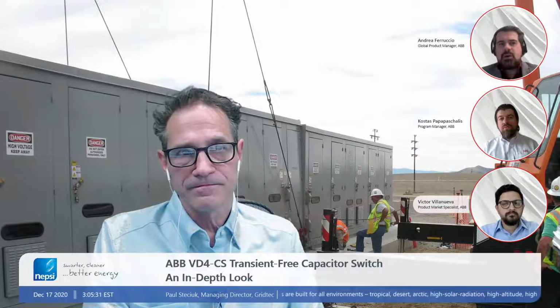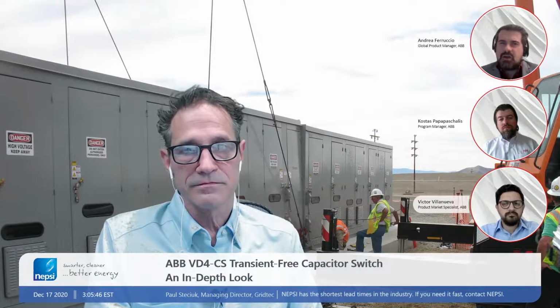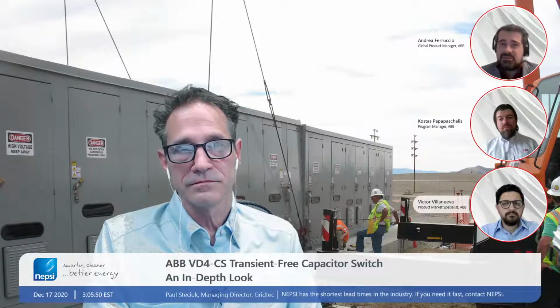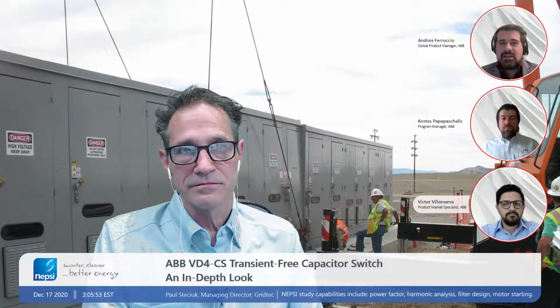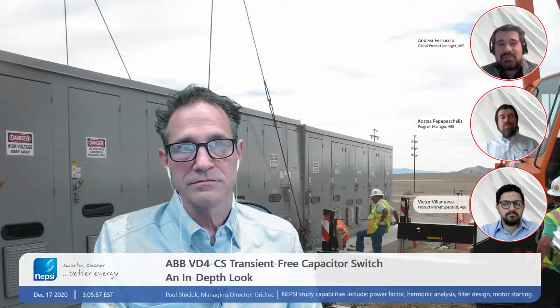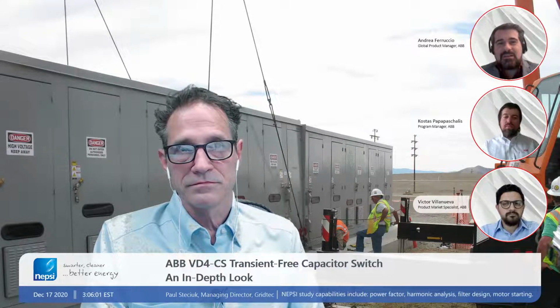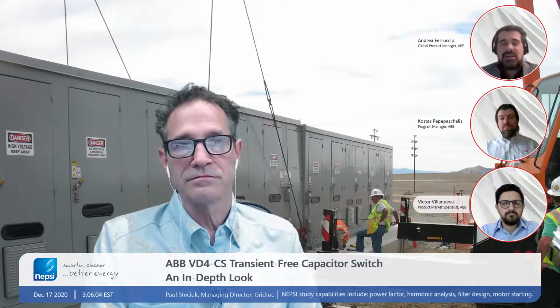The VD4-CS counts on the input signal of this sensor as a reference for establishing and applying the synchronization strategy. I would say yes, there is no redundancy in case of a faulty sensor. However, we have tested this sensor under really severe conditions, and I would say it is basically guaranteed—again like the servo motor and the capacitors—for the entire mechanical and electrical life of the VD4-CS tool. So in principle, yes, there is just one sensor, not on all three phases, just one, because according to the assumptions, once we have the reference from the first phase, we can assume and establish the value instant by instant of the other two phases.